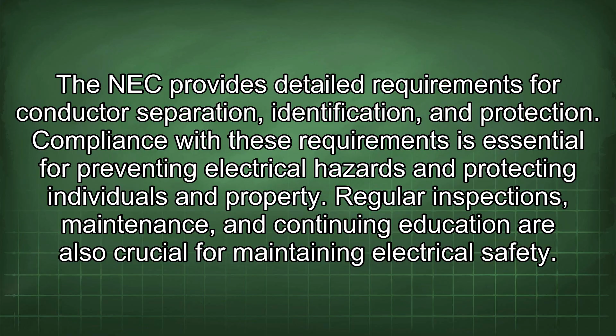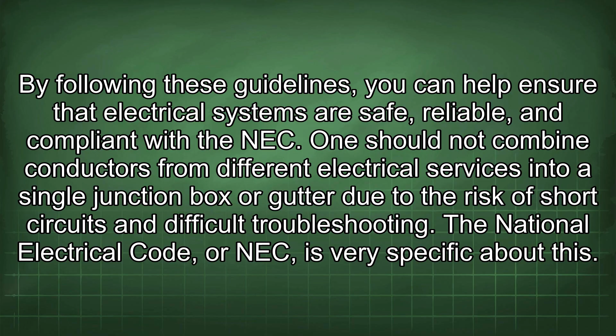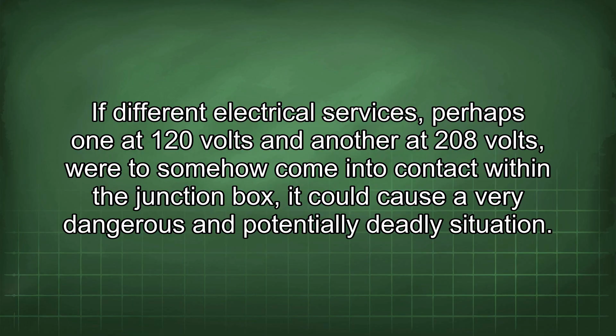One should not combine conductors from different electrical services into a single junction box or gutter due to the risk of short circuits and difficult troubleshooting. The National Electrical Code, or NEC, is very specific about this. If different electrical services, perhaps one at 120 volts and another at 208 volts, were to somehow come into contact within the junction box, it could cause a very dangerous and potentially deadly situation. The installation could fail, or something could be dropped, and all it takes is one small point of contact for there to be a problem.